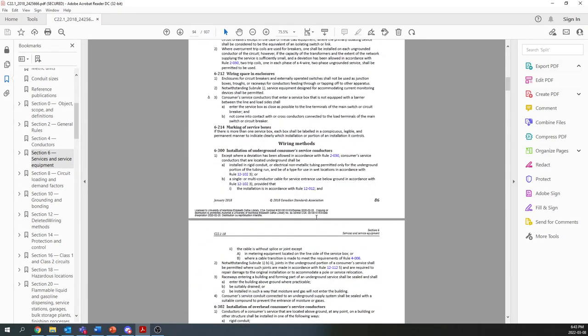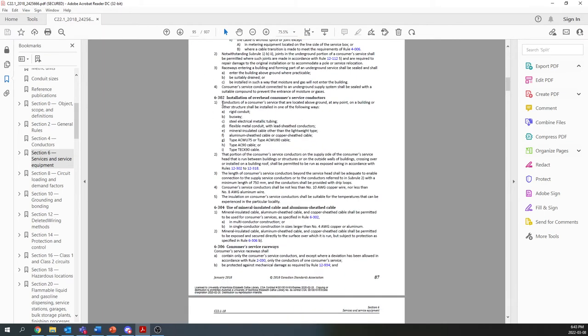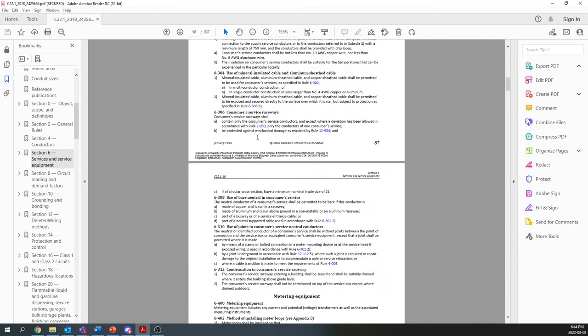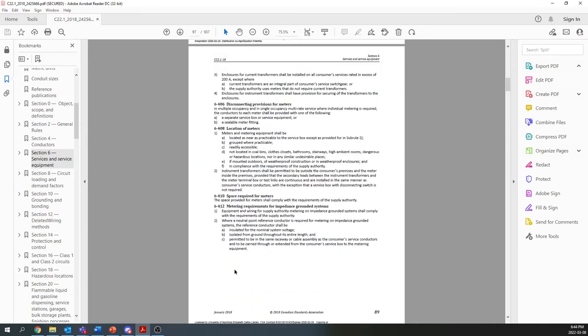Other things covered are wiring methods. Service conductors have to be protected because they are not fused. Upstream of your main disconnect, if those conductors were to get harmed in some way, if you have a utility connection they go directly to a transformer. Some of you will know that, depending on the size of your transformer, you can have a whole lot of short circuit current available at its output, and generally the transformer itself is not fitted with an overcurrent protection device. So you can have a big arc flash, big fire, if those conductors somehow get harmed. So the service wiring has to be protected, and it's very important. Metering equipment is also covered, and that's pretty much it.